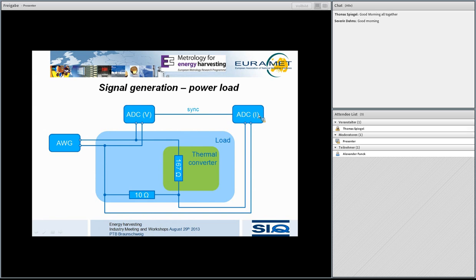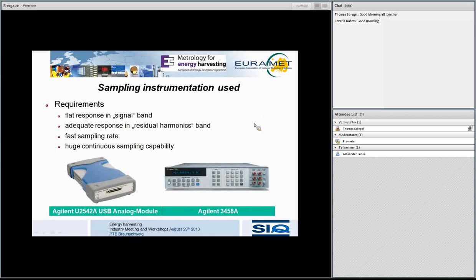And of course, the samples need to be synchronized to measure the power. For the sampling instrumentation, INRIM used the Agilent U2542A analog module, an ADC converter, and we used the well-known 3458 Agilent multimeter, which is extremely accurate, and we know it very well. The requirements on the instrumentation were that we should have a flat response, especially in the signal band where we have strong components. We have to have adequate response in the residual harmonics band, where the power does not affect our values so much. We should still have a response, but it is not necessary to be as accurate as in the low frequency band.